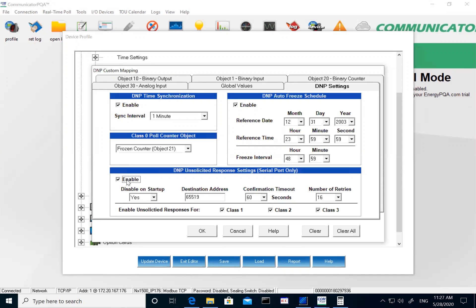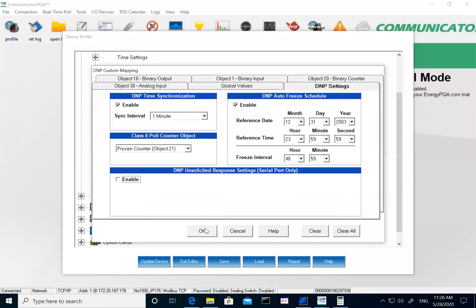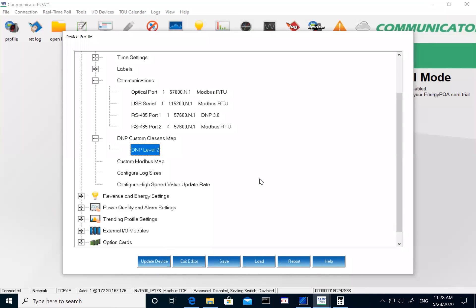You can also set up unsolicited responses. If you have hundreds of DNP devices on your network and want to be notified as soon as one generates an event or alarm, rather than having your software poll all hundred meters, the meter can send you a notification. This is something the meter sends out without any request from the master. You can enable this, set up the destination device address, DNP address, timeout, and which class to use. For now I'll leave it disabled.